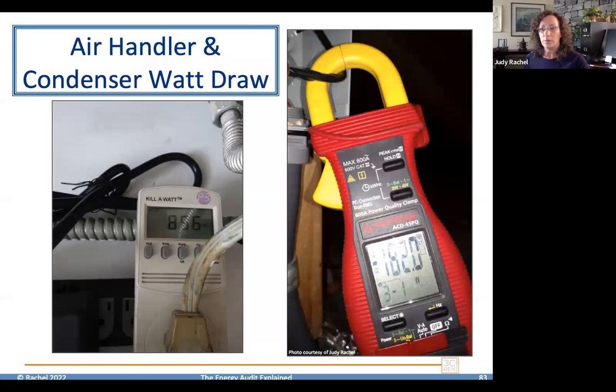Then there's finding out how much energy these pieces of equipment are actually using. Typically we can use something like a Kill A Watt meter to find out how many watts the air handler is using when it's turned on. And then we need a power quality gauge to measure at the condenser how much energy the condenser is using.